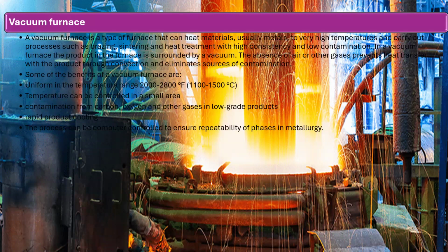Vacuum furnace. A vacuum furnace is a type of furnace that can heat material, usually metals, to very high temperatures and carry out processes such as brazing, sintering, and heat treatment with high consistency and low contamination. In a vacuum furnace, the product is surrounded by a vacuum, the absence of air or other gases, which prevents heat transfer with the product by convection and eliminates a source of contamination.